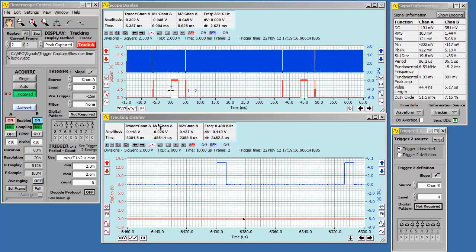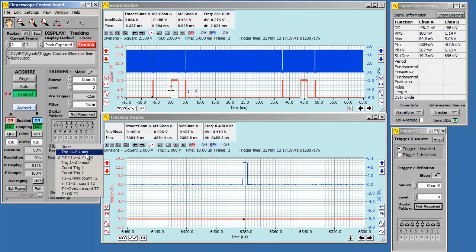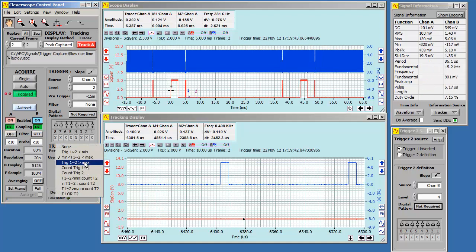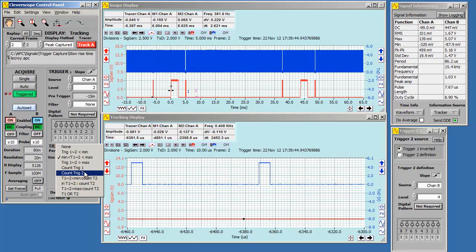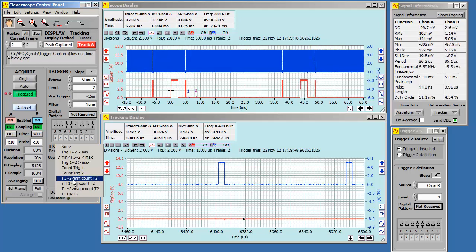We've been triggering on the time period between triggers. You can trigger on the period being less than a value, in a range, or more than a value. You can also count triggers. Finally, we can also trigger on a period and then count a trigger.